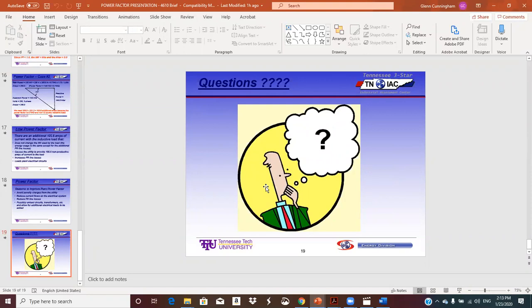So the cost-effective measure is to put capacitors right before they measure your electricity, and that's what people usually do. Though a lot of people correct it at the MCC instead. It's either at the MCC or one big bank at the meter. But if you do it at the meter, it doesn't unload the circuits out in the plant, it just unloads it from the point of capacity. So if the power company's here, the power plant's here, your meter's here, you put them right here, and you get the unloading from the capacitor back to the plant, but that doesn't help you out in the plant where circuits are still loaded.